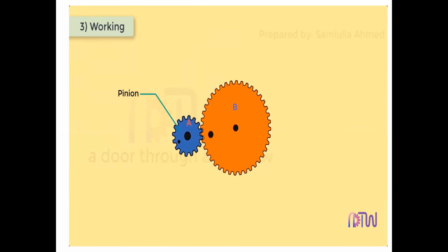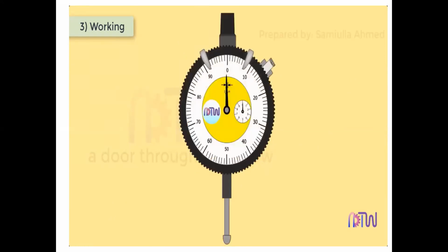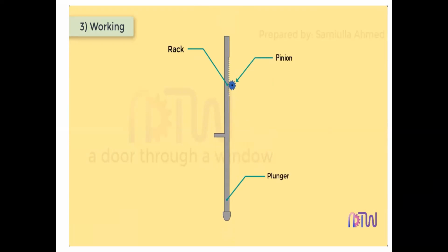With this basic understanding, now we can see how the magnification of the plunger is achieved in the dial gauge. To obtain the necessary high magnification ratio in this instrument, a gear and pinion arrangement is used, arranging the gear train in a manner similar to a clock movement. There is a plunger which is a perfect sliding fit in its own bearings. This carries a rack which accurately meshes with a pinion. The rotation of the plunger about its own axis is prevented by a pin attached to it, which is located in a slot in a rack guide.